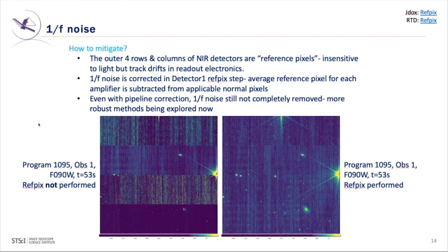However, when you do perform the ref-pix correction step, you get an image that looks like this, and it looks a lot better. However, you can see there's still a lot of residual noise present in the spectrum. And so this is a pretty short exposure. It's less than a minute. And so the problem is very much exacerbated here with a low background.